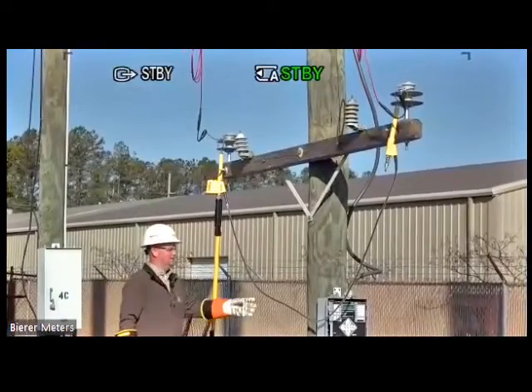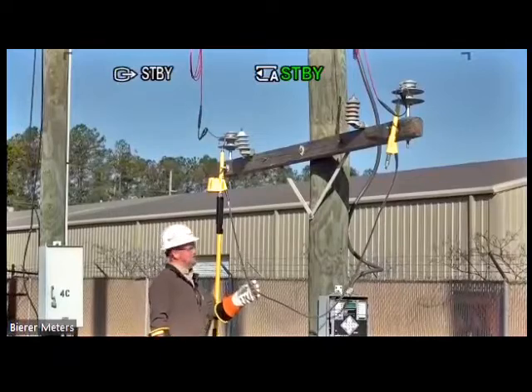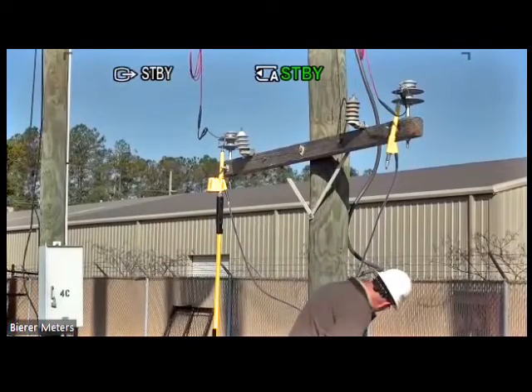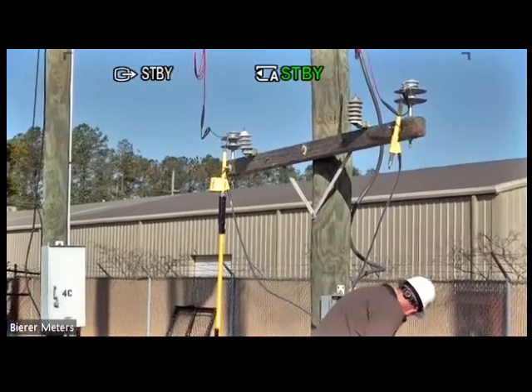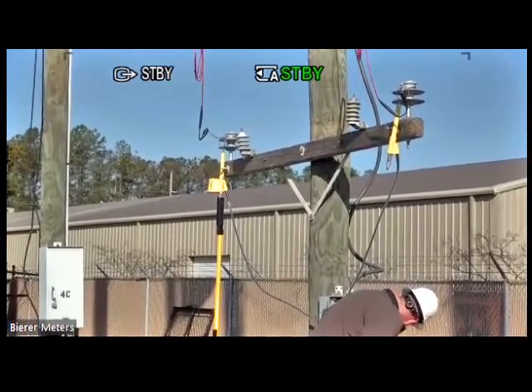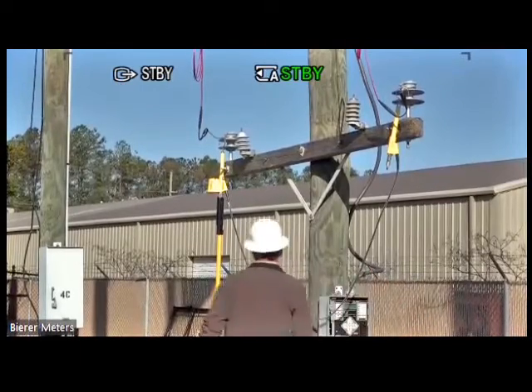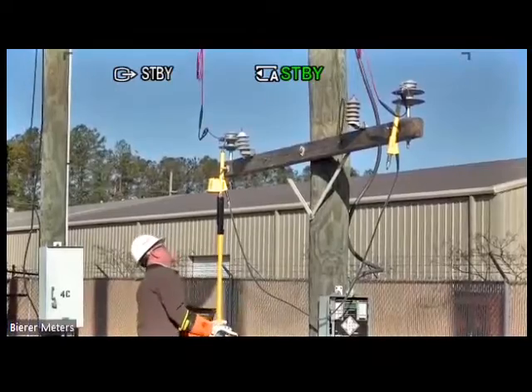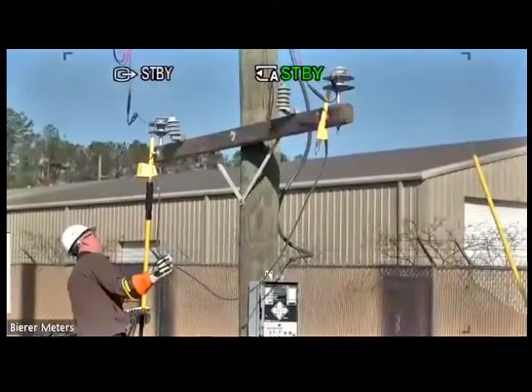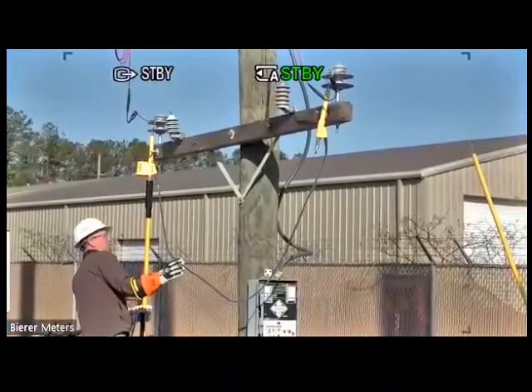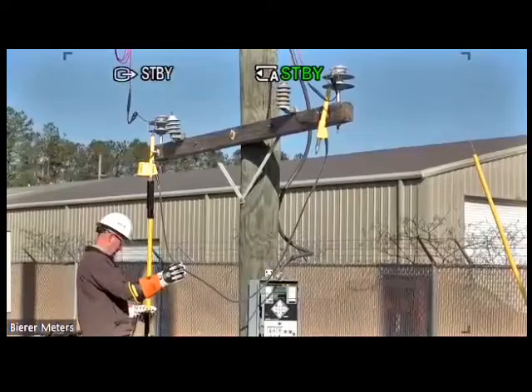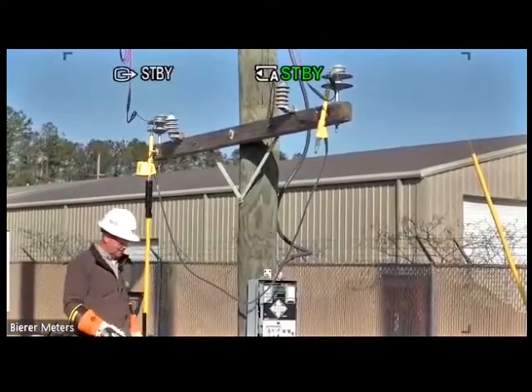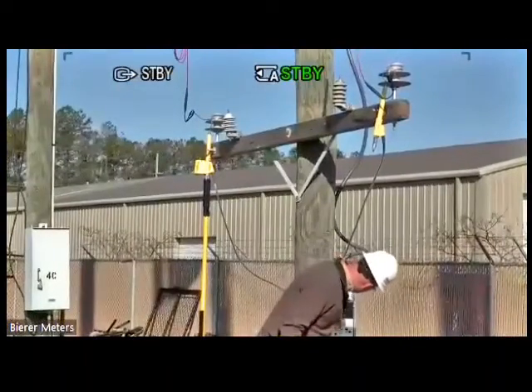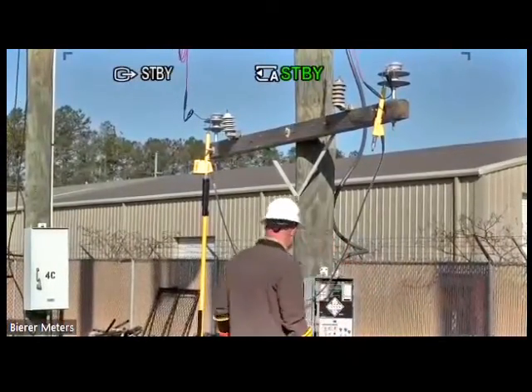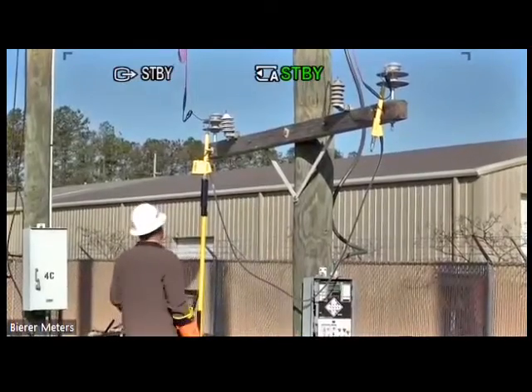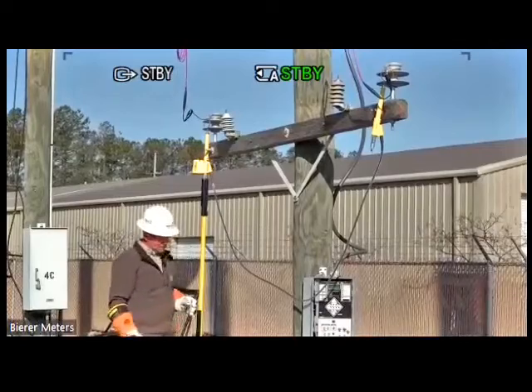So right now, I have less than 10 volts. So if I take this device and I raise it a step, I want to see what the difference of potential goes to. And it goes to 70 volts, 75 volts. Okay. So there is the in step, out of step. I'm verifying that the light in this regulator, the display, the neutral light in this Cooper controller is actually correct. So I want to make sure that light is correct, or the dial.